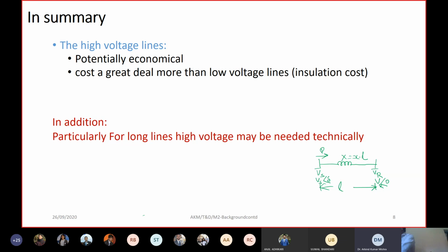I hope you remember, if you try to express the correlation between Vs, Vr, and P, the very popular power transfer equation for a lossless line is P equals Vs times Vr, divided by total inductive reactance X of the line, times sine delta - where delta is the phase angle difference between the two end voltages. Vs and Vr here are only the magnitudes of the voltage at the two ends, and X is the total reactance of the line. I hope you remember this well.